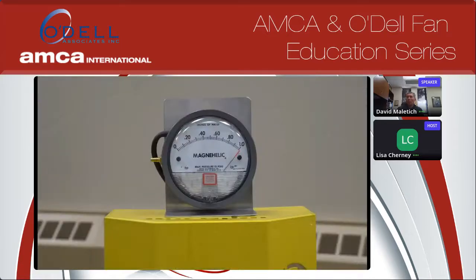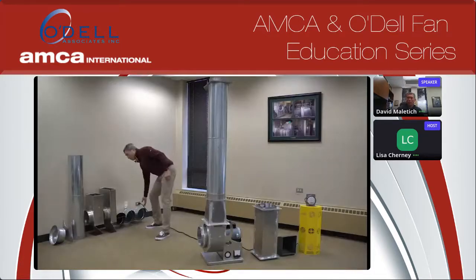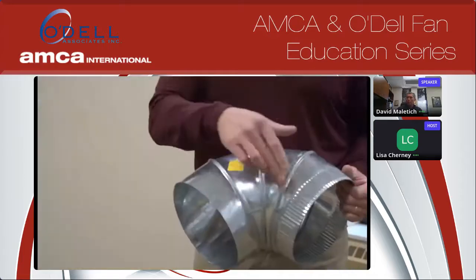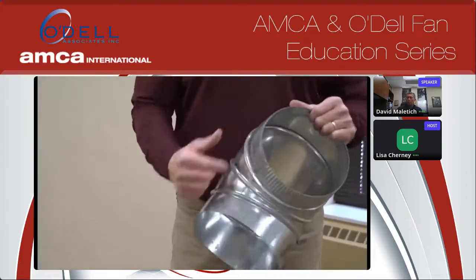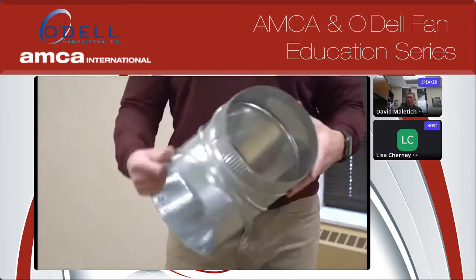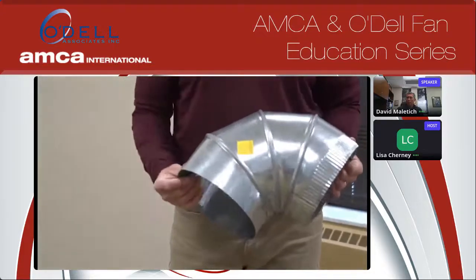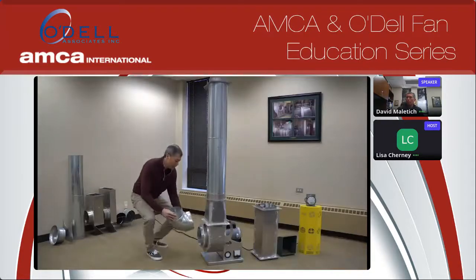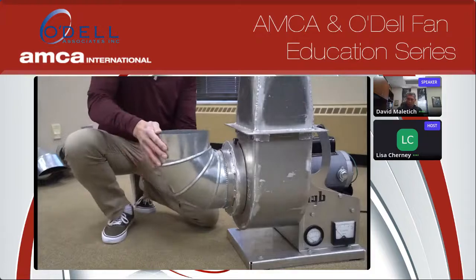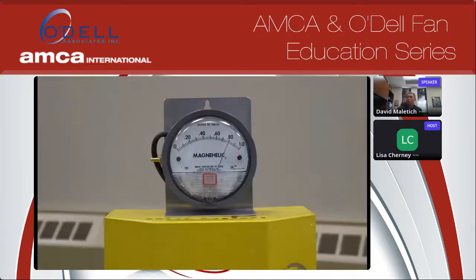So the first thing we're going to do is grab a piece of ductwork. It's a 90-degree elbow, and you can see there's no vanes inside the elbow, and we're going to see how it affects the fan's performance. So we put it on the fan's inlet, and looking at the Magnehelic gauge over there, you can see that the fan performance has gone down significantly just by putting a 90-degree elbow on the inlet of the fan.